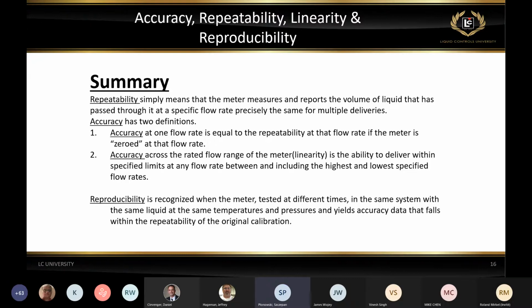Again, just quick definitions. So there on the screen, repeatability means that the meter measures and reports the volume that's being delivered precisely the same way on multiple deliveries. Accuracy has two definitions. Accuracy at a single point, let's say at our highest flow rate, and that accuracy, if the meter is zeroed out, will generally equal the repeatability of the meter. So if we calibrate a meter and the meter is exactly at zero, the accuracy will equal the repeatability of that meter. The second is accuracy across the range of flow, which is linearity. Again, it's accuracy from high to low flow rate, something that's commonly tested in the field. And again, we talked a couple of times already about reproducibility and what that means.